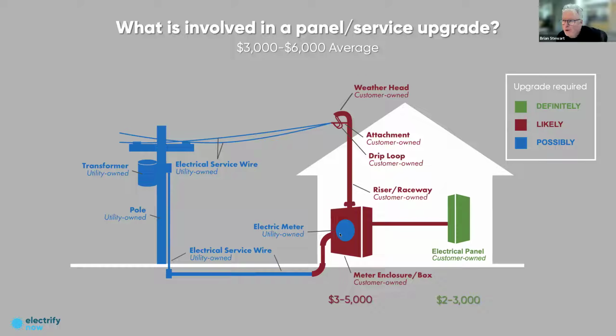If you looked at that meter and it said CL100, for sure you're going to need a new meter, and most likely some upgrading to the overhead wires. Utilities will do that free of charge up to a certain point, it varies by jurisdiction, but usually there's some allowance enabling them to make modest upgrades. But it's not uncommon to end up in a situation where they look into it and decide they need to put a new transformer on your neighborhood service to give you that upgraded service from 100 amps to 200 amps. Because you're the one triggering this, you have to pay for that, and it can be thousands of dollars.